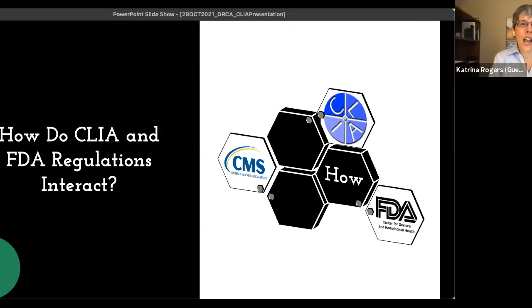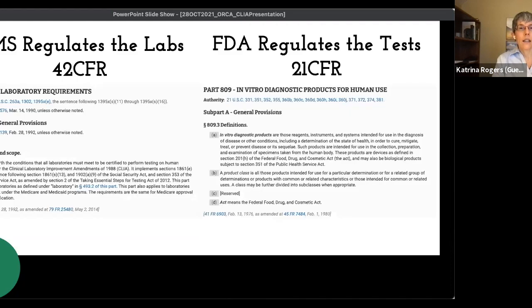So how do those CLIA and FDA regulations interact? Firstly, these regulations are all established under different legislative mandates. You'll remember that I mentioned that CLIA was established under the amendments to the Public Health Service Act. The FDA regulations for medical devices were established in 1976 through an amendment to the Federal Food, Drug, and Cosmetic Act. And so that means that the regulations are under different CFRs as well. CMS regulates the labs under 42 CFR Part 493, and the FDA regulates the actual tests themselves under 21 CFR Part 809.